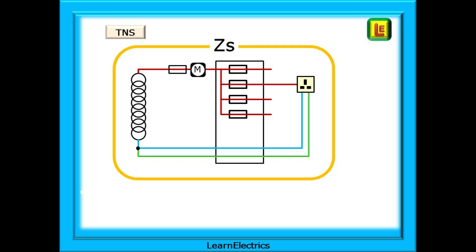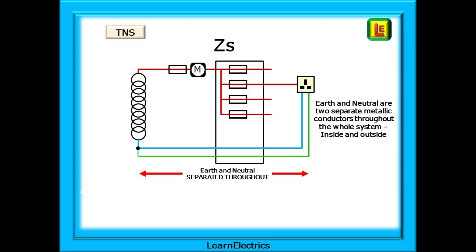Starting at the bottom of the supply transformer, on the left, we can see that there is a physical connection between the Earth and the Neutral at the transformer. But, from that moment, from the moment that they leave the transformer, Earth and Neutral each have their own conductor. From now on, they never share. All the way to the consumer unit, through the consumer unit, and on to every point of use, they are kept separate. TNS, Earth and Neutral Separate.